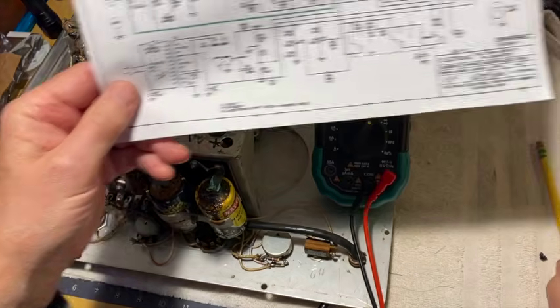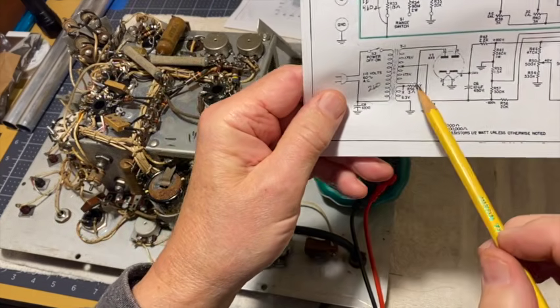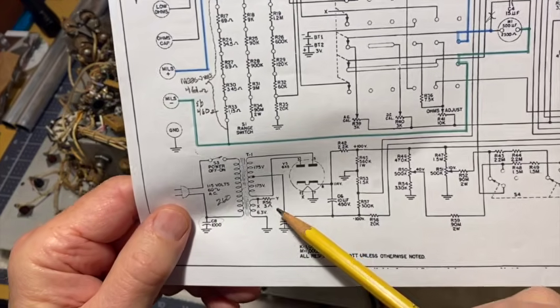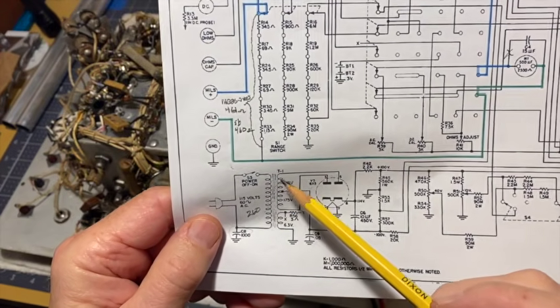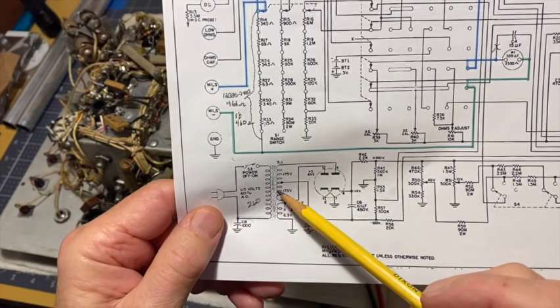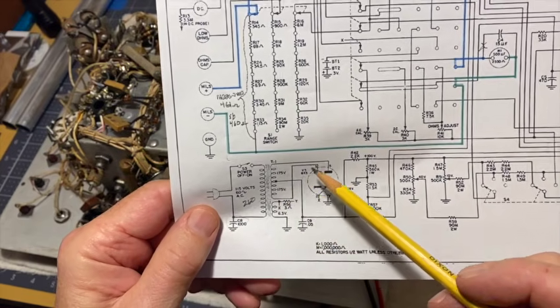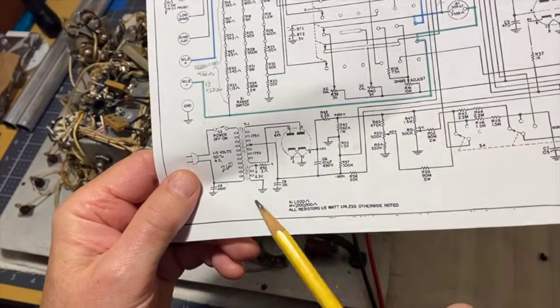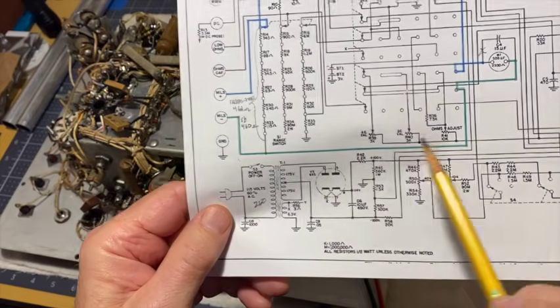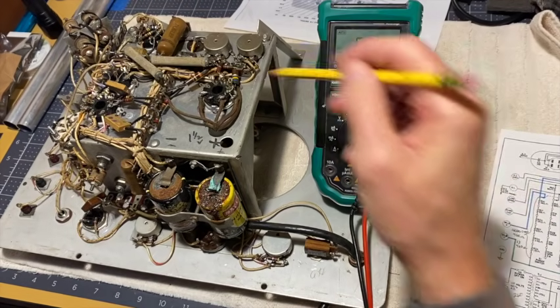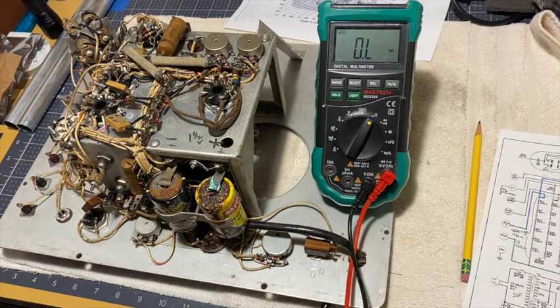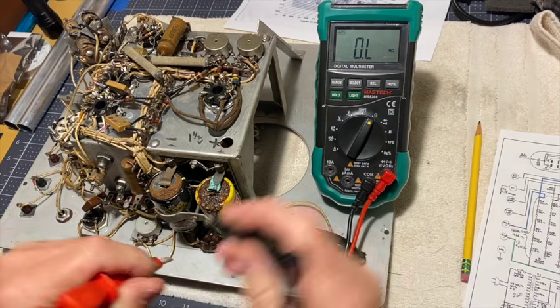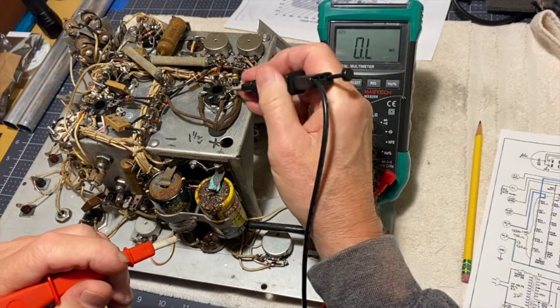Now we can check right here across the both ends of the center tapped secondary transformer by going to pin 3 and 5 of the rectifier tube. All the tubes are out of here, by the way - I took them all out and tested them, they're all fine. So here's pin 1, 2, 3.